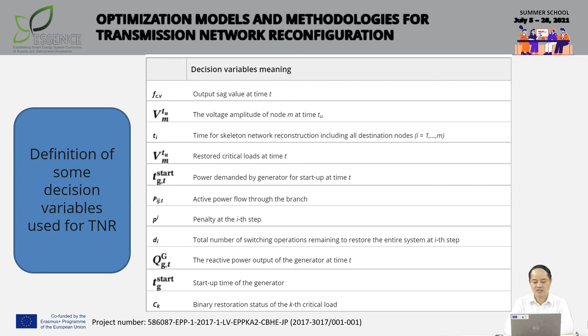The generator startup sequence plays a key role in the restoration strategy, determining the time consumed in power system restoration and accelerating the system recovery. In generator startup sequence, non-black start generators are cranked through the black start generator via transmission line.